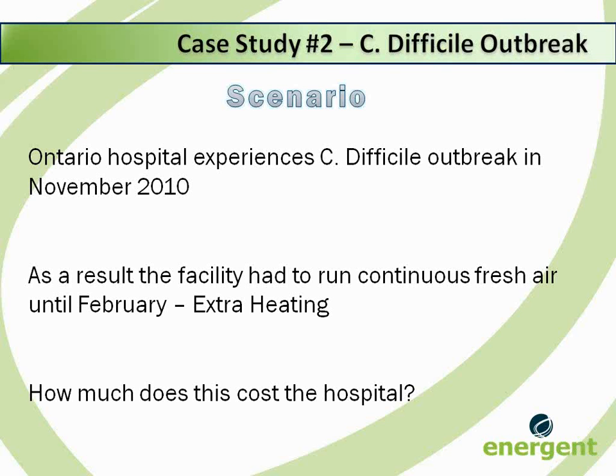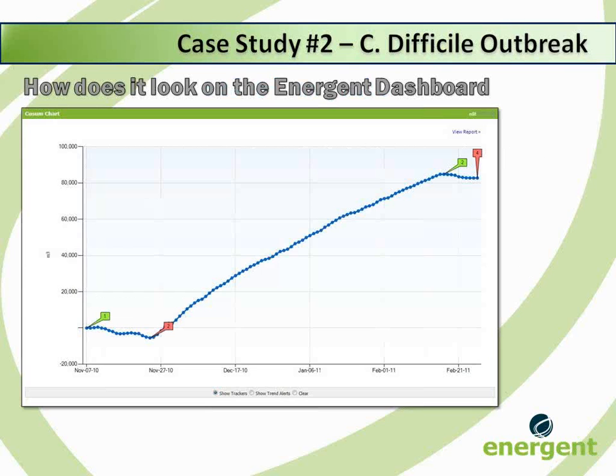Let's take a look at how it was presented on the Energent dashboard. As you can see, this hospital at the beginning had a slight decrease in CUSUM from the beginning of November to November 24th. On the 24th, they switched to 100% fresh air, which required extra heating. This continued until February 17th. By mid-February, the CUSUM restarted on the downward savings trend, as was going on prior to the outbreak.